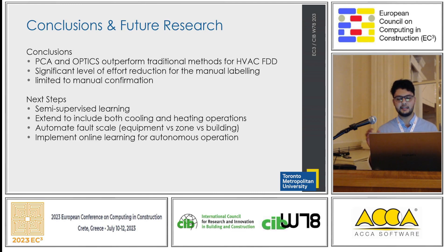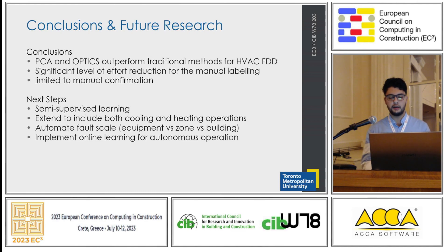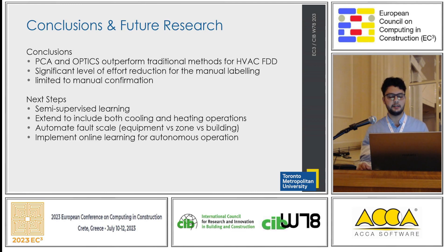We showed that OPTICS provides excellent results for fault detection. Using this method, we can automatically label our dataset for further development of our classification algorithms. One limitation is the relatively small sample size — just three pieces of equipment in one building, with analysis limited to cooling operation only. Currently, we are working on extending OPTICS to all FCUs in the target building and labeling detected faults to create a training dataset for our classifiers, and also extending the work for fault diagnosis. To improve the reliability of the FDD method, we are incorporating a semi-supervised learning method like label spreading. We acknowledge the support of NSERC, Fuse Forward, and the Toronto Metropolitan University Facility Management Team. Thank you very much.